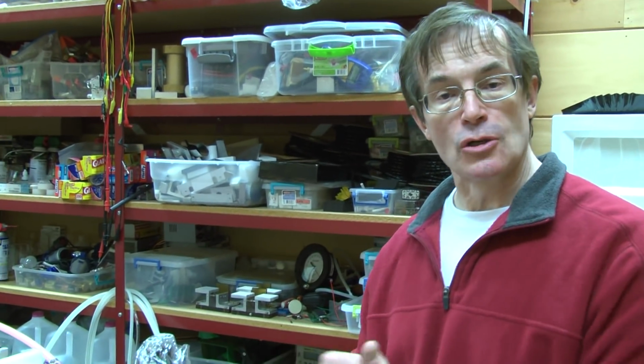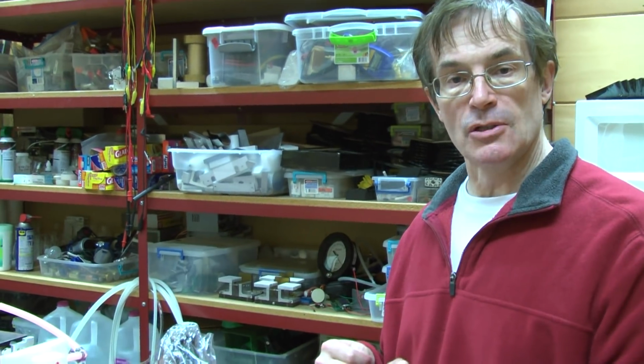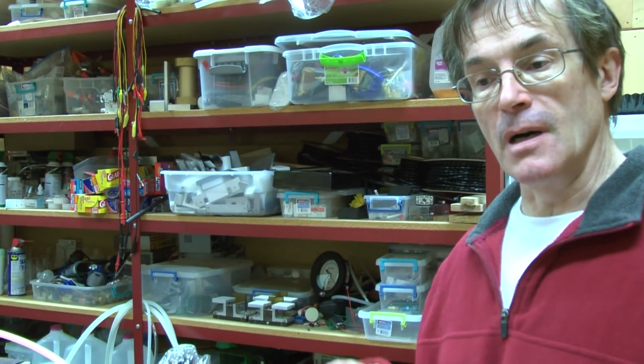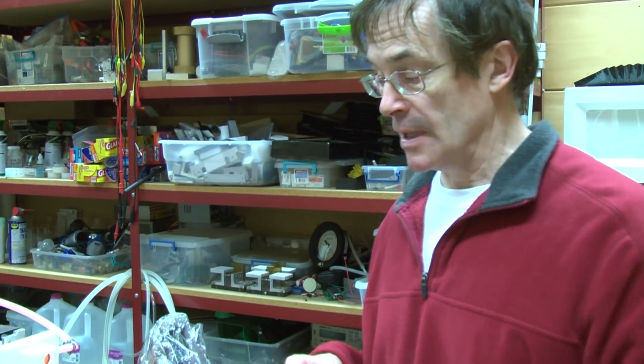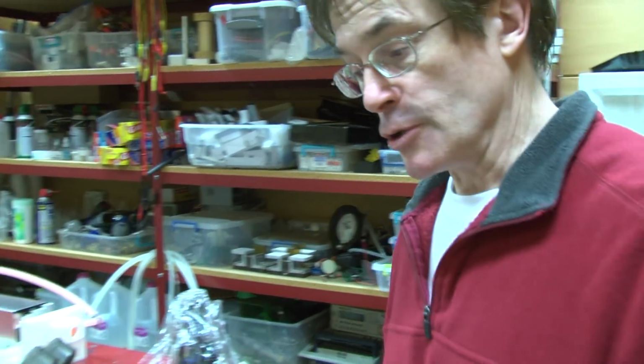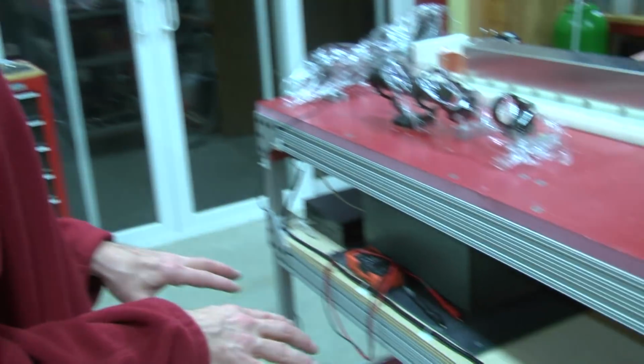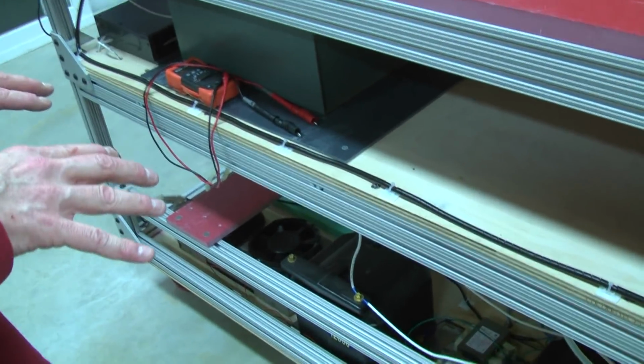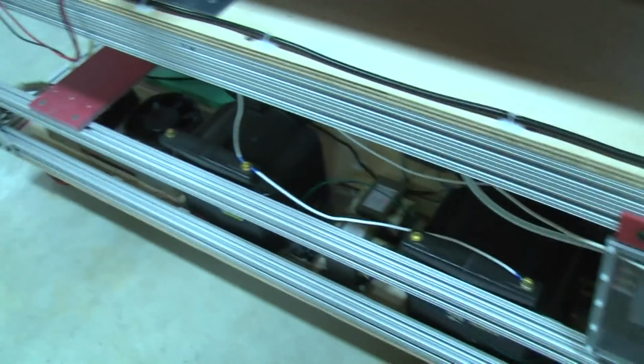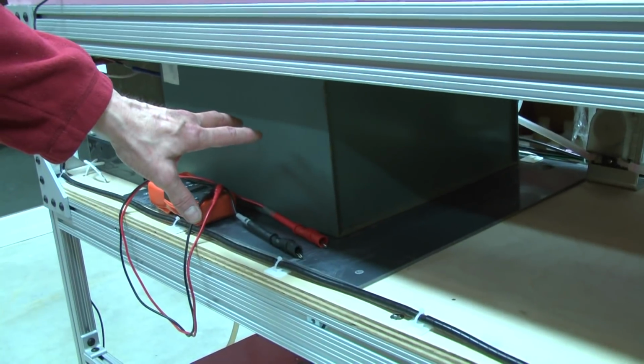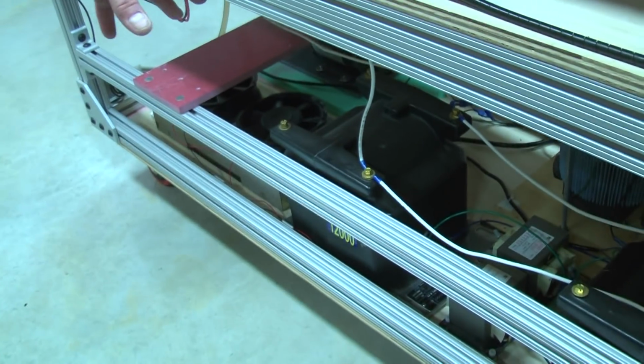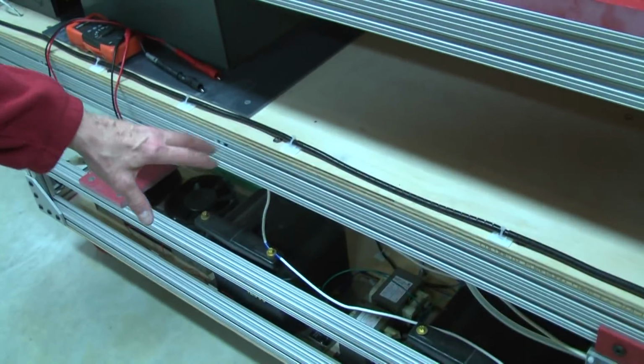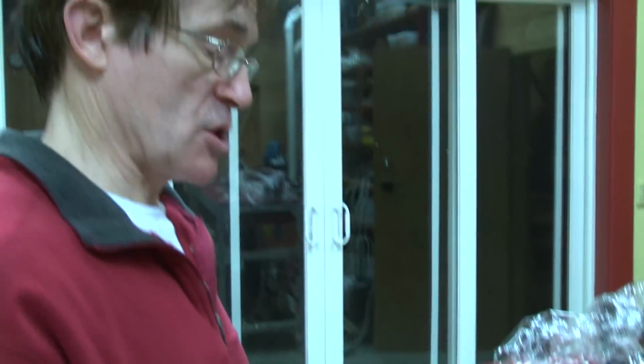However, it is a little empirical. I mean, you have to figure out what time is going to reach what voltage, but once you've established that, it's a set factor and you know exactly what you're going to get each time you charge the laser. You still have a problem though when you charge the transformers from the line. The transformers are charging what looks to them initially almost like a dead short. And so they would draw 30 plus amps each from the line, blow the circuits, potentially overload themselves.